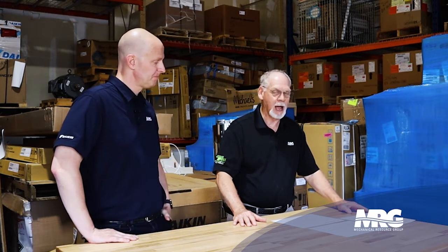Also, there's several different types of plastics. Most of the times they'll use a CPVC. Sometimes they'll use a PVC Schedule 40. They have one that's called a foam core that you cannot use because it's not solid pipe. It's got a foam core in it, and it will melt. So you've got to be real careful on what you're doing and knowing what materials you should use on that.